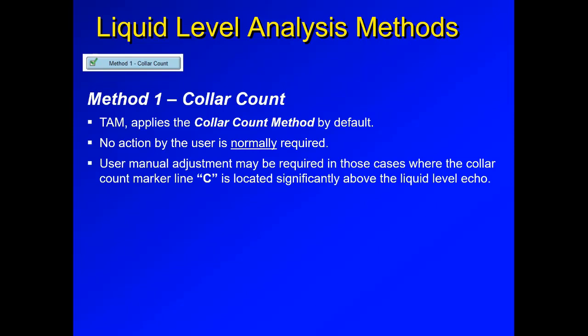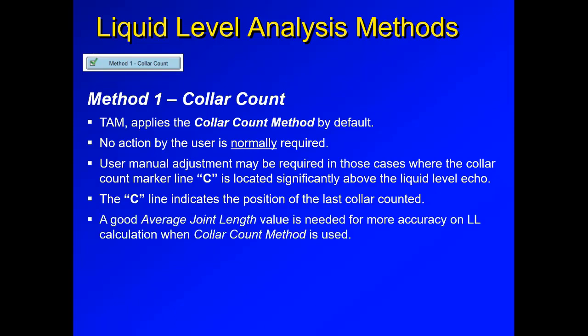The user may have to manually adjust the collar count based on where the C line is located. The C line indicates the last collar counted in the trace. The software tries to see collars in the acoustic trace, but after some point it may no longer see any collar down to the liquid level. Depending on where the C line is, you may need to take some action to improve the quality of the shot.